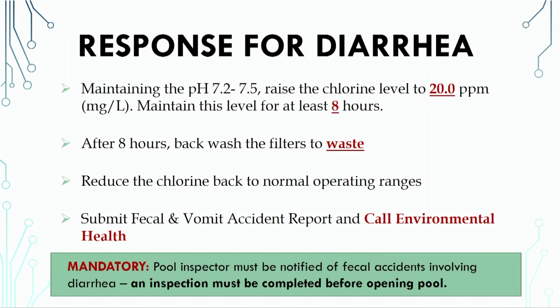After 8 hours, you want to backwash the filters to waste, and then you want to reduce the chlorine back to normal operating ranges. And then you want to submit the fecal and vomit accident report, and you want to call us here at Environmental Health, as it is mandatory that we are notified of any type of accident like this, as an inspection will have to take place before you reopen the pool.